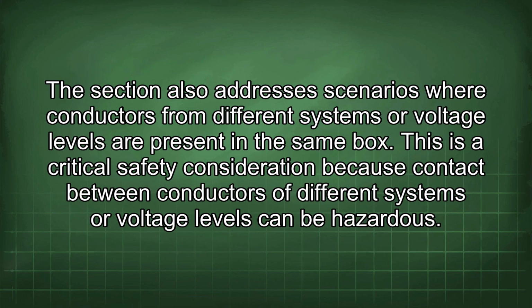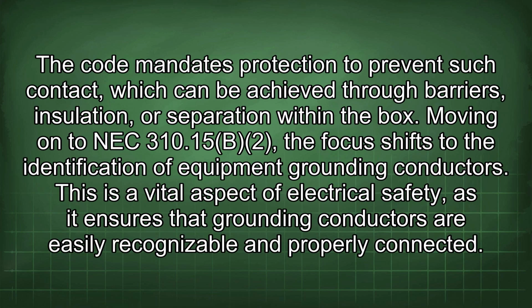The section also addresses scenarios where conductors from different systems or voltage levels are present in the same box. This is a critical safety consideration because contact between conductors of different systems or voltage levels can be hazardous. The code mandates protection to prevent such contact, which can be achieved through barriers, insulation, or separation within the box.